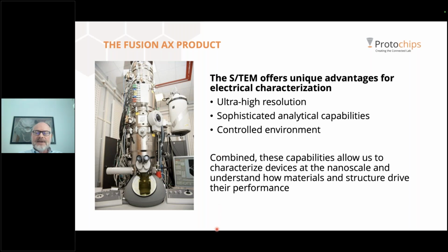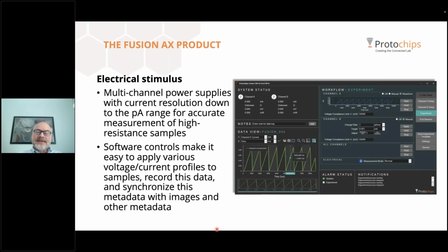It also provides you with a very controlled environment. It's like a giant Faraday cage that protects your sample and your measurement from outside noise. Now combined, this is a set of features that we can exploit to characterize these devices at the nanoscale and understand how materials and structure drive performance. Now, the electrical stimulus is provided by one or more power supplies with current resolution down to the picoamp scale. And this is important because by their nature, samples in the TEM are small and thin. And even really high current densities can still mean that you're measuring very low currents.